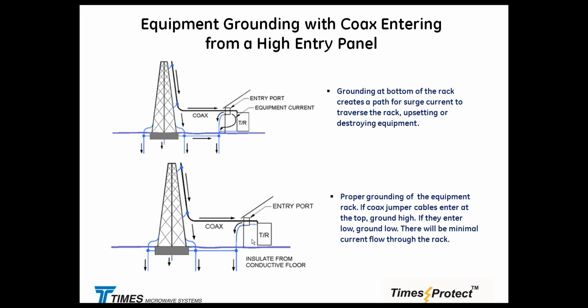If you've got a raised floor of some sort with a grid or whatever, which might be tied to the building steel, you might have some potential for current sneaking the other way and returning itself if it sees lower impedance on the return here than it would see here.